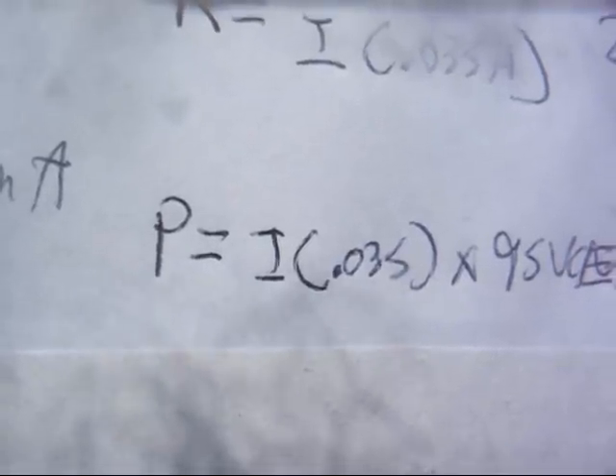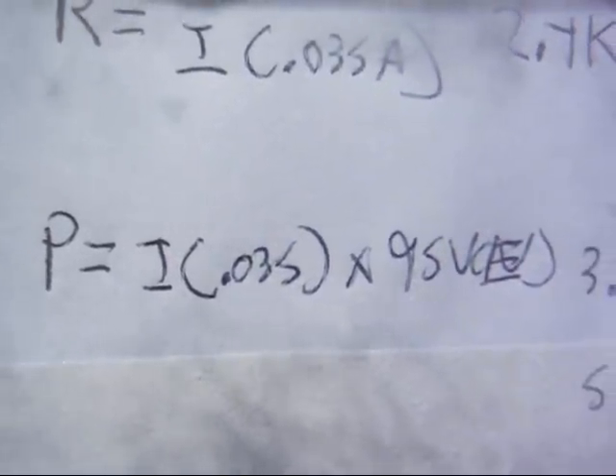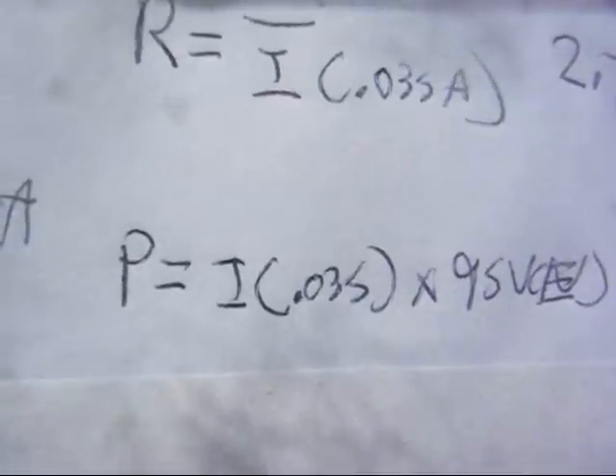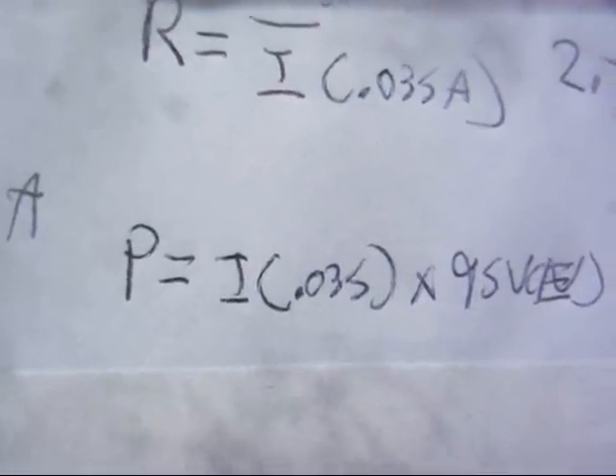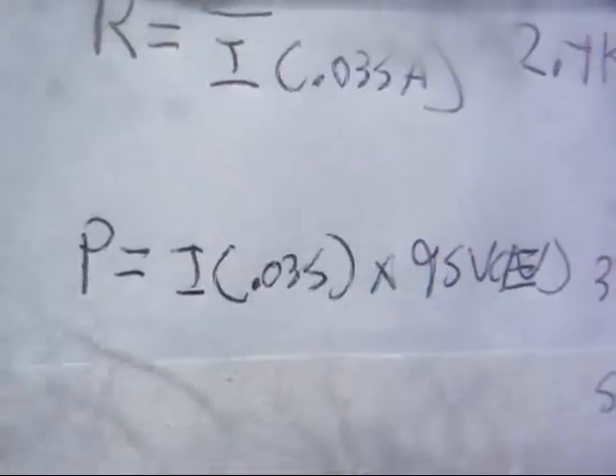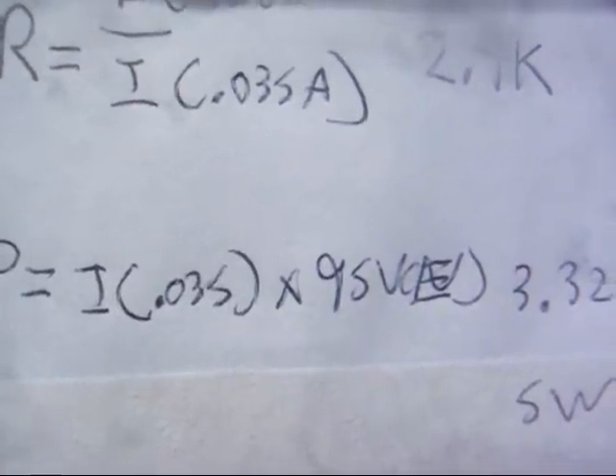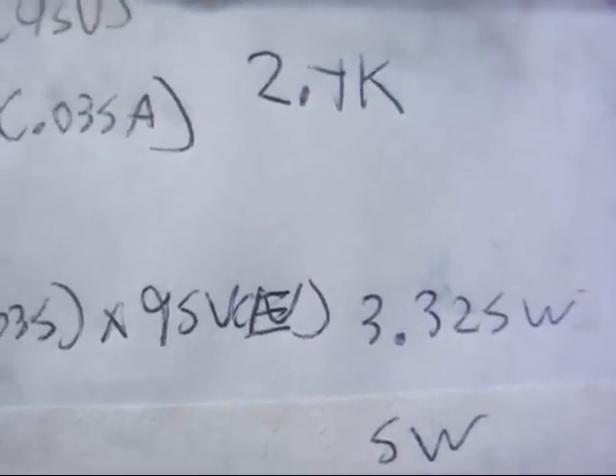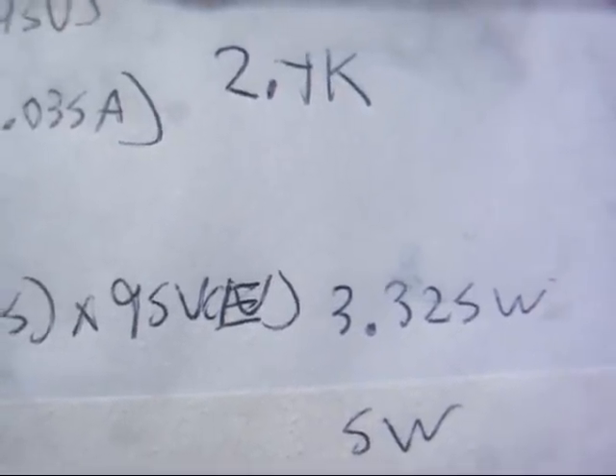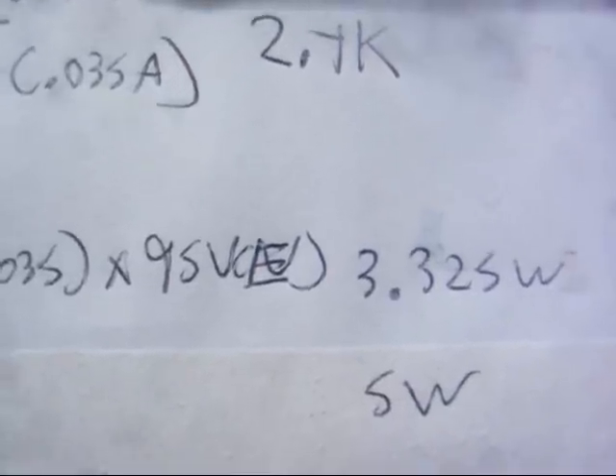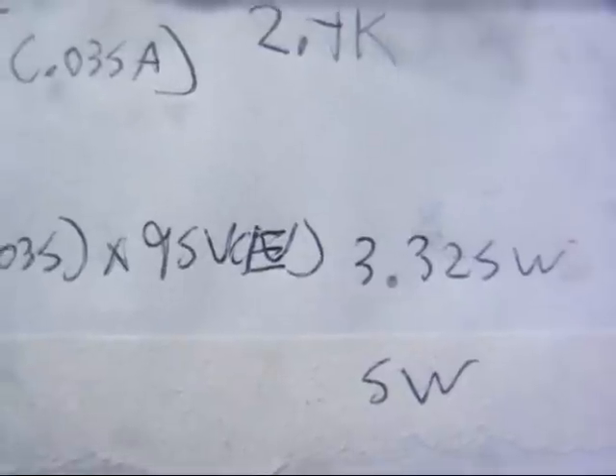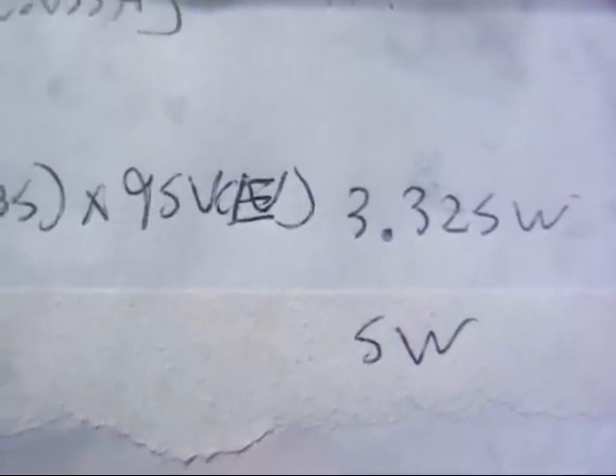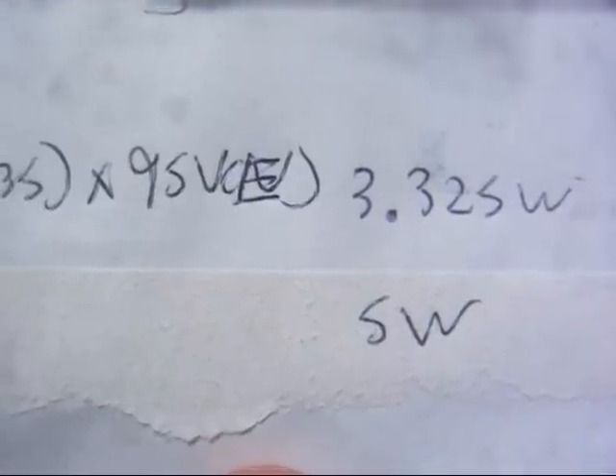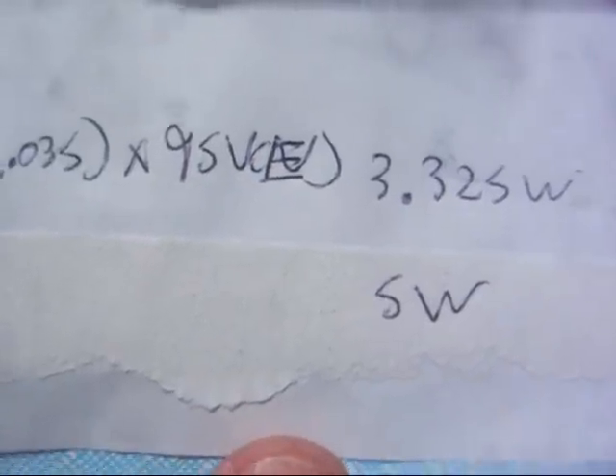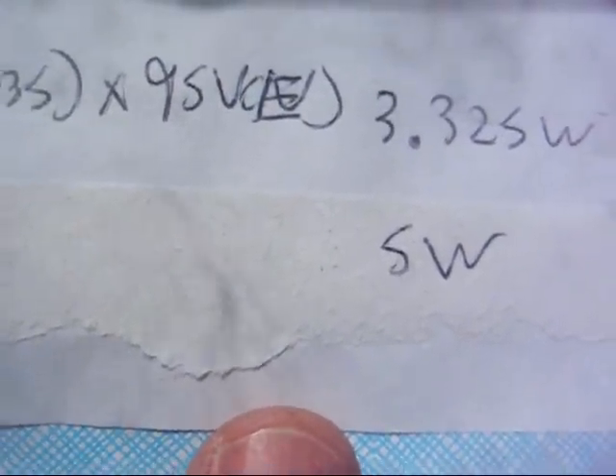And power in watts equals current I times voltage E, and in this case 0.035 amps, which is what we measured, times 95 volts, which is what we want to drop, and that gives us 3.325 watts. So we'd want to go up to the next available wattage resistor, which would be 5 watts. So I'd want to use at least a 5 watt, maybe a 10, maybe a 20, maybe a 25, just whatever I can come up with.